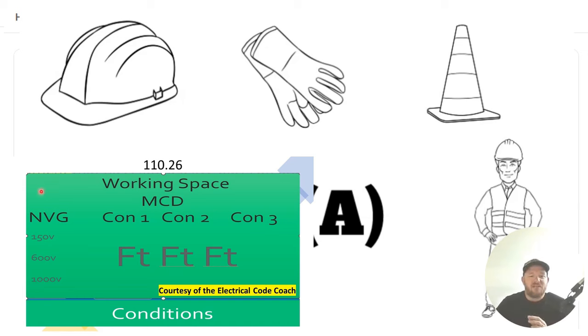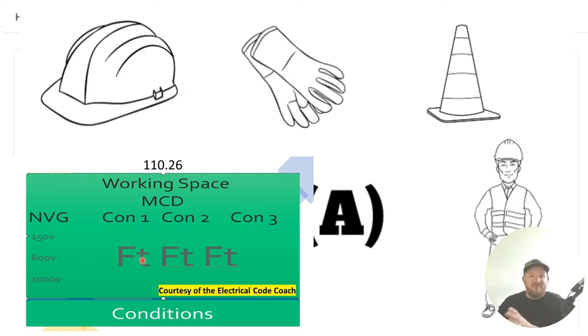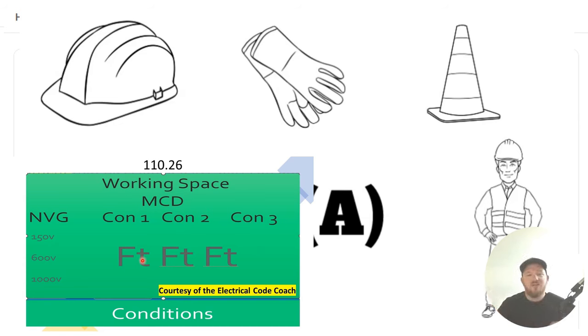On the left-hand side is going to be our nominal voltage to ground. Across the top is going to be depending on our condition. And then here, when we tee off with those two items, we're going to find how many feet of working space we're required to have.